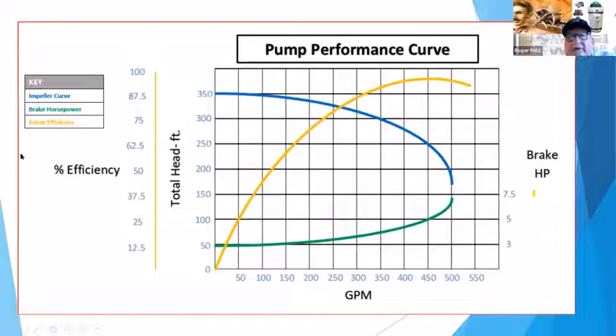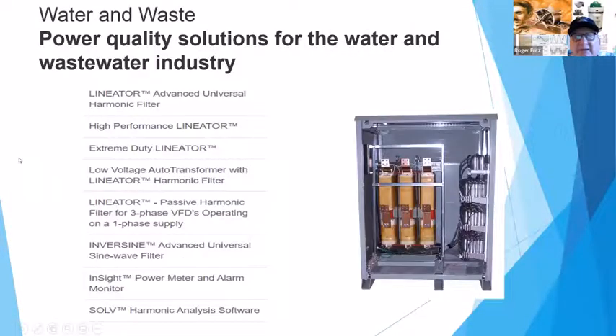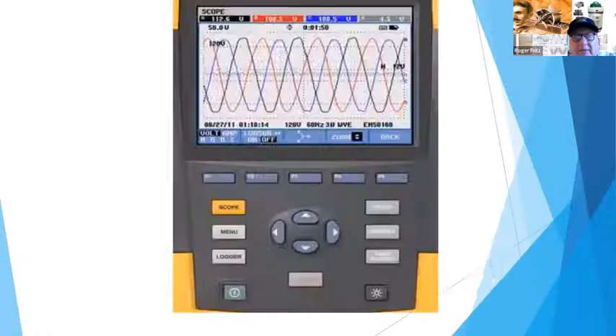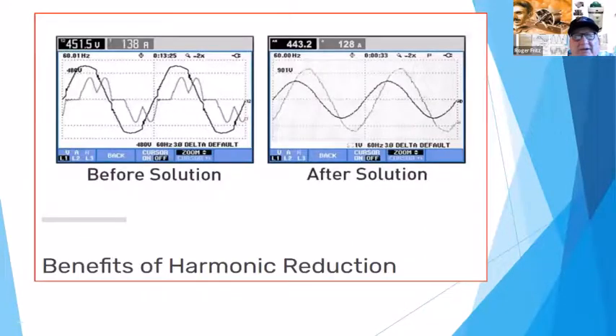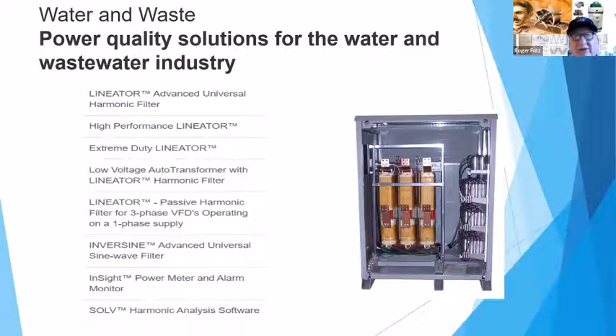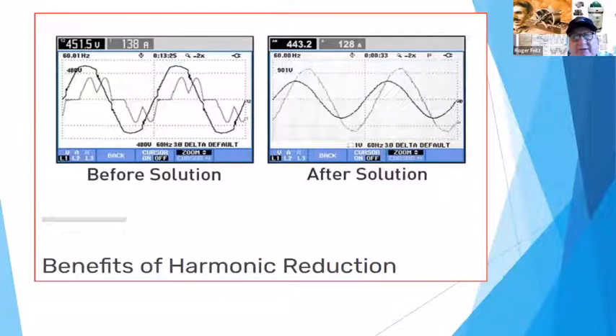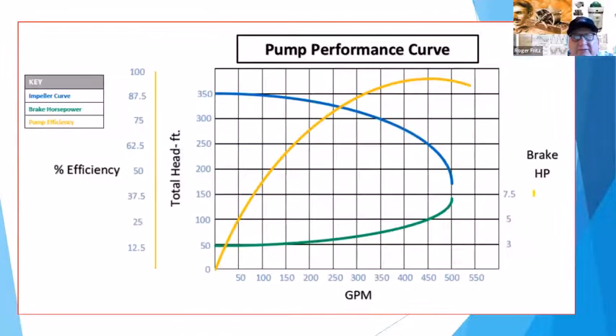But one area that I want to talk about is which one of the components to use. Do you use a cross-line starter? Do you use a Y delta starter? Do you use a part winding starter? Do you use a soft starter, or do you use VFD technology? Well, something that's very, very important is understanding that, yes, VFDs will save power, because as you slow it down, the horsepower drops by the cube. Also, the GPM goes down.